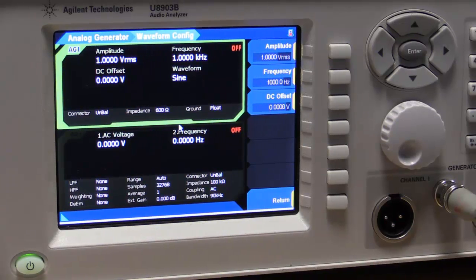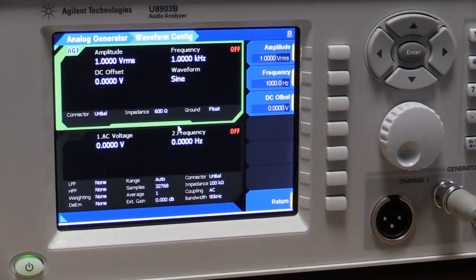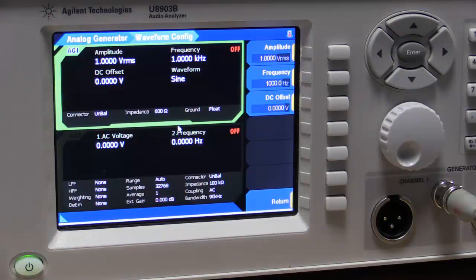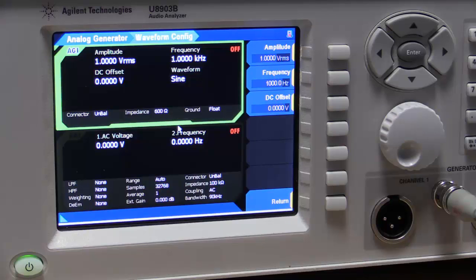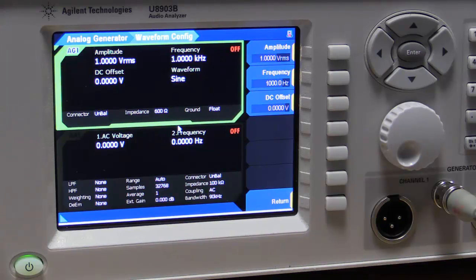Okay, so we'll now go and make a real-time measurement based on the example we've just shown. This is the U8903B in its basic configuration where you're looking at the generator and analyzer. You would use this for your more traditional audio measurements such as level or distortion, cross-talk, things like that.